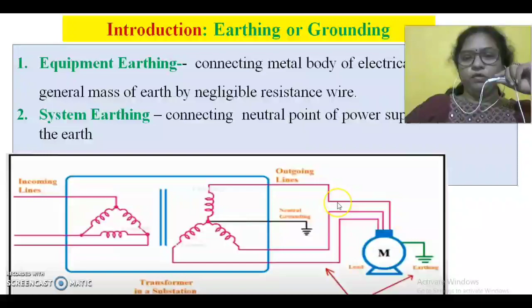Here you can see this is the system with earthing. The equipment's outer frame is connected to earth, and the supply system neutral is grounded. When a person comes in contact with this outer frame, and if any live terminal touches this metal frame, then the earth fault current will flow through the earth, so the human being will be safe.